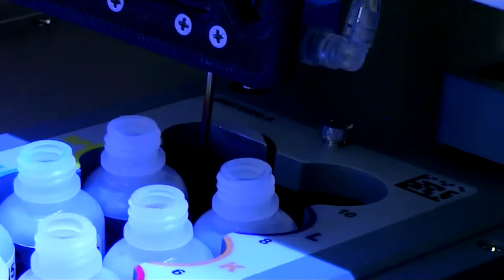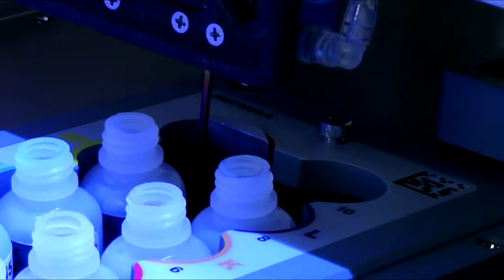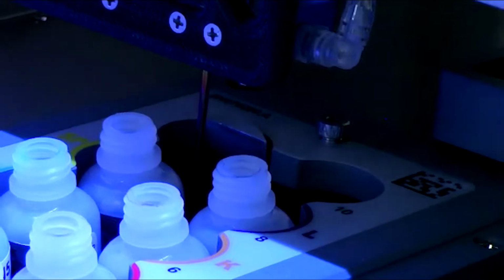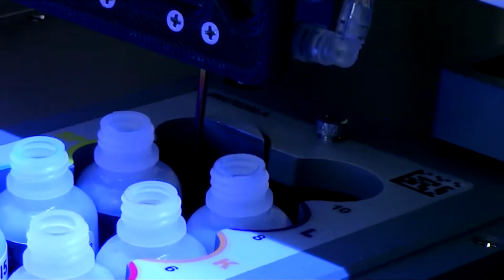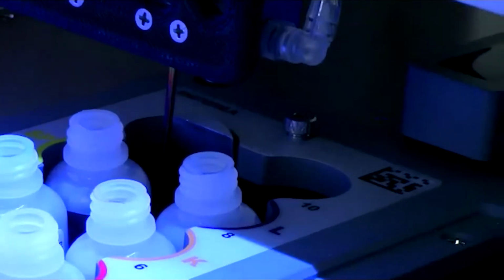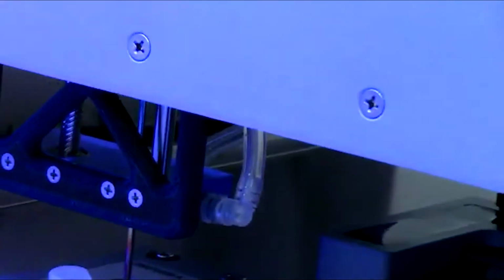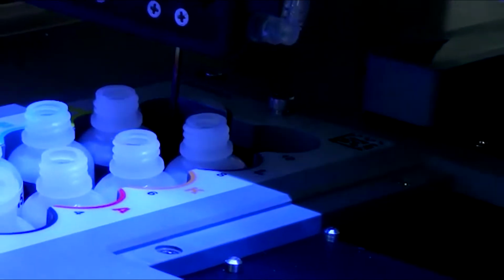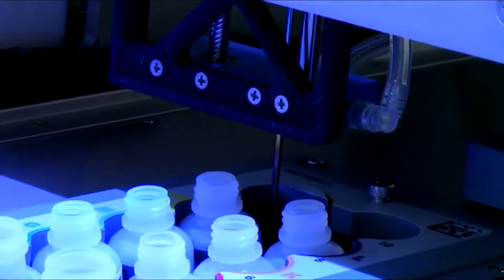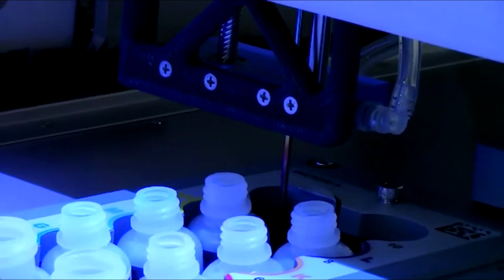Many of your calibrations are resistance type calibrations. So it doesn't take a whole lot of effort, really minute adjustments. And it still works very well within those limits of the resistance type jigs. We have a lot of things based on feel and a lot of upper and lower limits, and a lot of our calibrations are robust. The more sensitive positions are going to be the pipette positions, but especially with our claw, there's a lot of give there where they only have to be so close to really work. So they're pretty easy to find a good position where everything is going to work very smoothly.